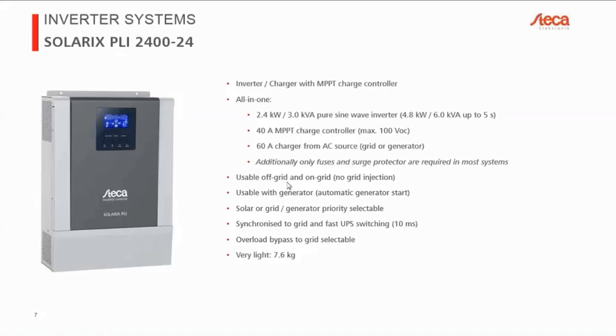Or you can use it in an on-grid scenario or with a generator, and you can be sure that there will never be any injection into the grid. It is physically impossible for this device to inject into the grid, even for just a few milliseconds. It cannot do that. We also have an automatic generator start. So we have a relay contact on the inverter on the bottom, so you can give a signal when the battery voltage is low to start a generator.